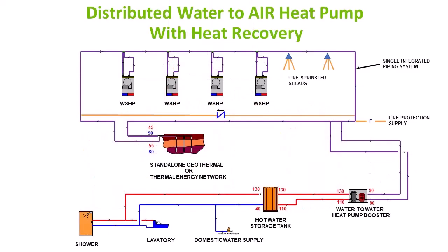Okay, we're storing the water at 130 degrees. Legionella, you kill it at about 124, so we store the water at 130 to kill the Legionella, then pump it out through the building. What would you store it at, 140? Then we'll store it at 140 - we don't care. We've been doing 130 systems for quite some time with no problems, but if you want to store it at 140, store it at 140. And those heat pumps can do that easily, right? Yeah, not a problem, good question.